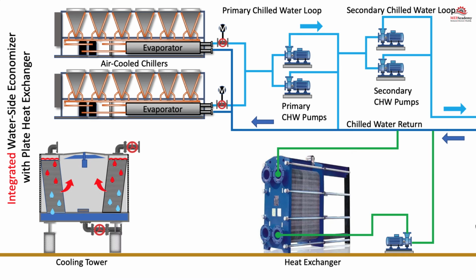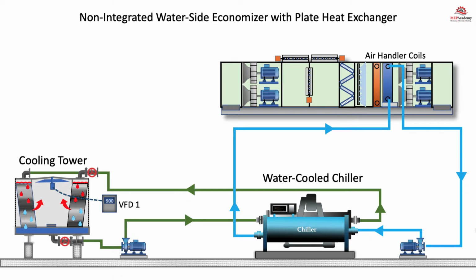Then a cooling tower is added to the system for heat rejection, along with a pump to pull cool water from the basin and send it into the heat exchanger, where it will pick up heat from the chilled water return system. Then it will exit the heat exchanger warmer and be distributed at the top of the tower, where it will give up the heat to the atmosphere.